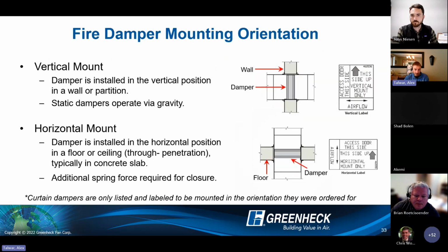Mounting orientation, I did cover that earlier. Just a little more in depth here on this slide. Obviously with curtain style products, if you have a static rated damper in a wall, we're not going to put a spring in there. It'll just close via gravity. Now, if you're putting that on its side and putting it horizontally in a floor, you don't have gravity working in your favor. So there are differences in the design of the product. So again, something we'll need to know up front. The product actually does come with a label on it, signifying if it's for vertical mount only or horizontal mount only. But of course, airflow, if it is a dynamic rated product, will always be both directions.